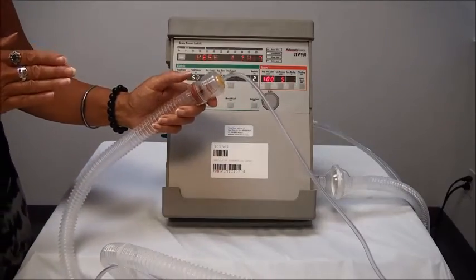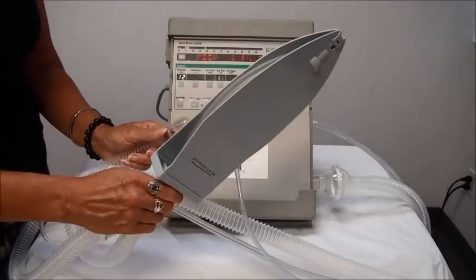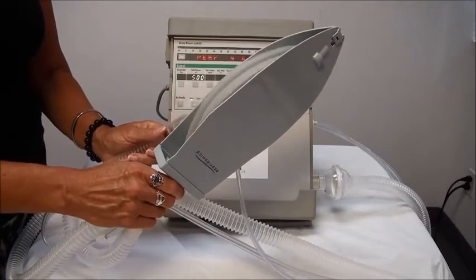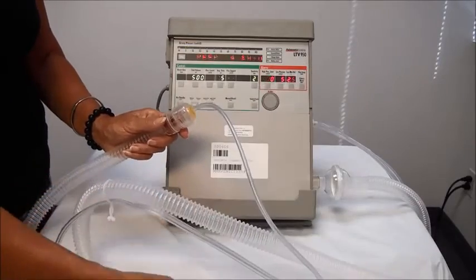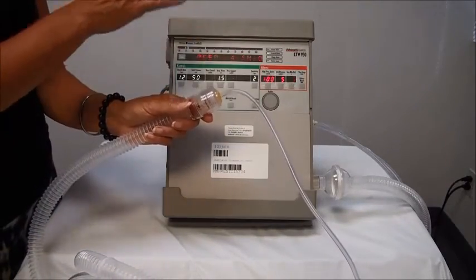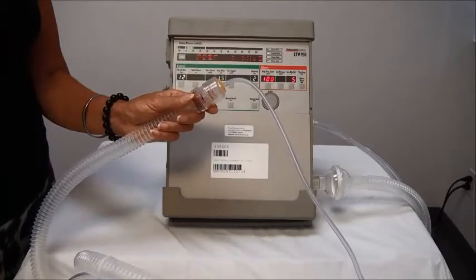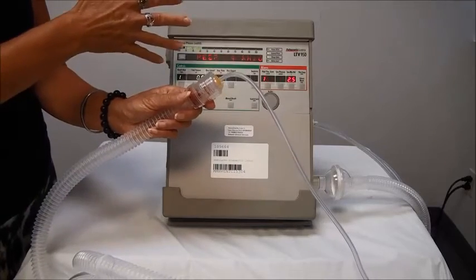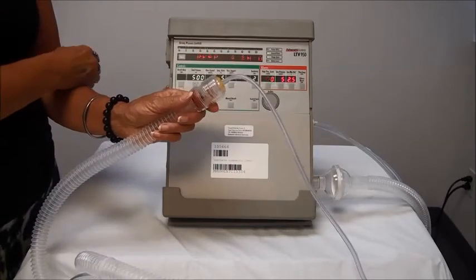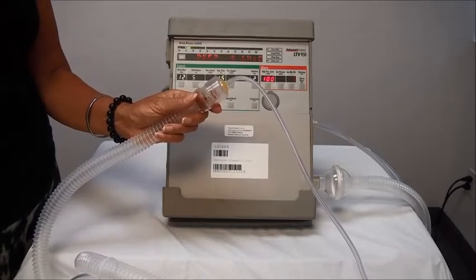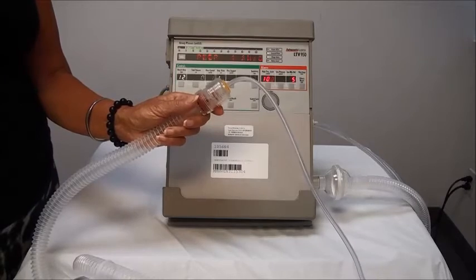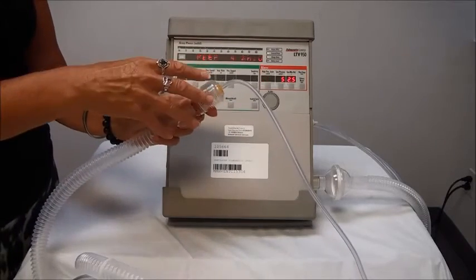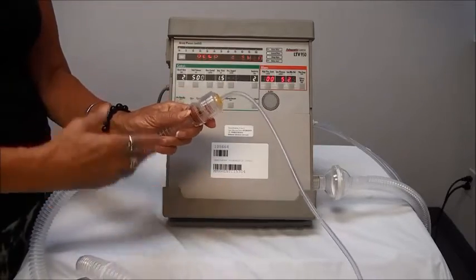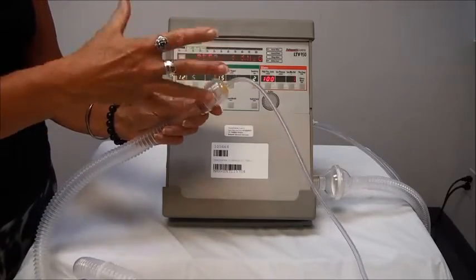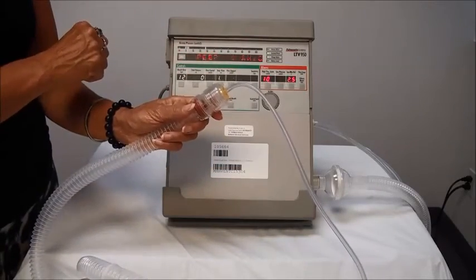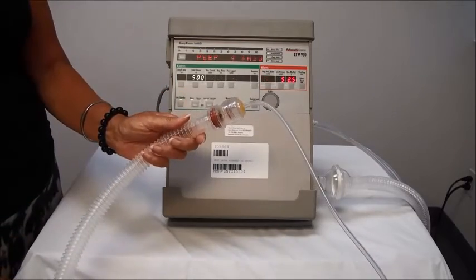One thing that's really important is that every client should have a test lung with their ventilator. It may look a little bit different than this, but it will be something that you can put on the ventilator to do any testing that you need to do. When you're setting your PEEP for the circuit, you want to make sure that you have it on the test lung. Because when you put this on your patient, your data readings will come back. They may come back differently just because of different things that are going on with your patient's airway, depending if you have the cuff inflated or deflated. So when setting your PEEP, make sure that you use the test lung, and then when you put it on your patient, as I said, your readings may be a little bit different, but you'll know that you have it set at the correct PEEP as what's ordered by the physician.